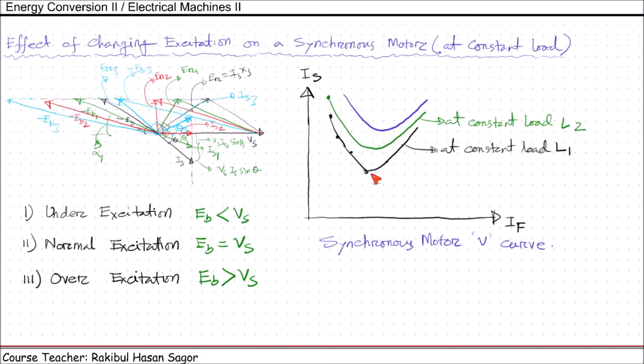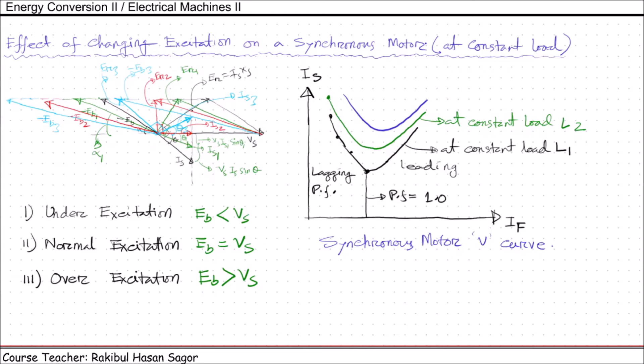Now for any particular load, you will get the minimum armature current, that is IS current, when the power factor is 1. So at this point, you will get the power factor equal to 1. The right side of this minimal current represents the leading power factor area, and the left side of this minimal current represents the lagging power factor area. So this is lagging power factor and this is the leading power factor.